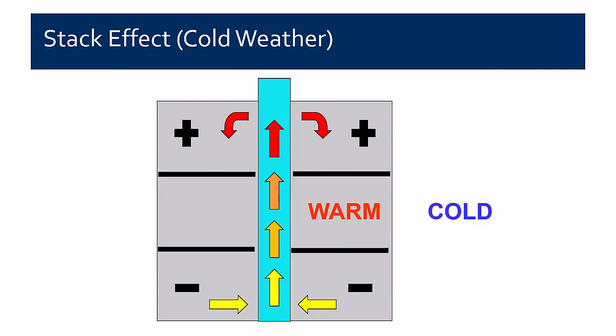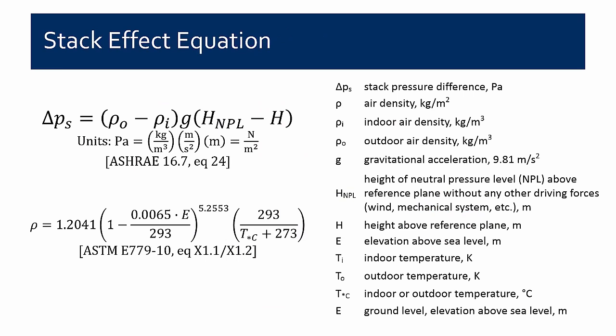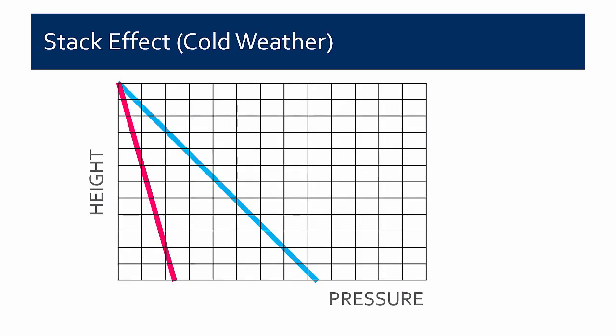Stack effect: in cold weather, stack effect causes the upper floors to be positive and the lower floors to be negative when you have a shaft connecting the building. Most buildings have some means for air to move up and down, so stack effect is fairly common. In cold weather, you have positive pressure on the upper floor and negative on the bottom floors. In warm weather, the opposite is true. The stack effect equation looks at the density of outside air versus inside air, with a conversion factor showing where the neutral plane exists.